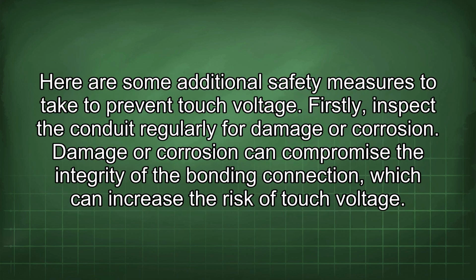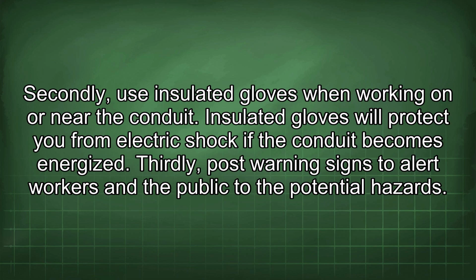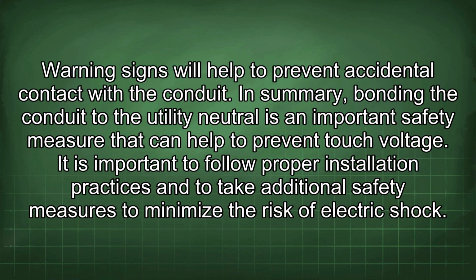Here are some additional safety measures to take to prevent touch voltage. Firstly, inspect the conduit regularly for damage or corrosion. Damage or corrosion can compromise the integrity of the bonding connection, which can increase the risk of touch voltage. Secondly, use insulated gloves when working on or near the conduit. Insulated gloves will protect you from electric shock if the conduit becomes energized. Thirdly, post warning signs to alert workers and the public to the potential hazards. Warning signs will help to prevent accidental contact with the conduit.